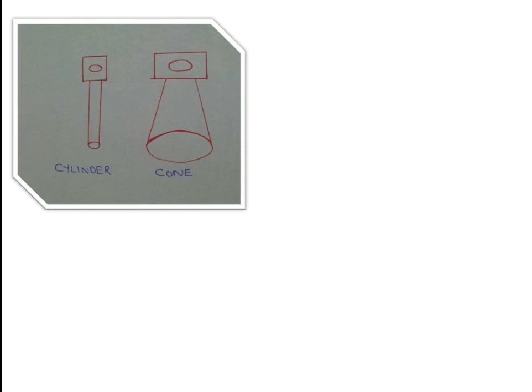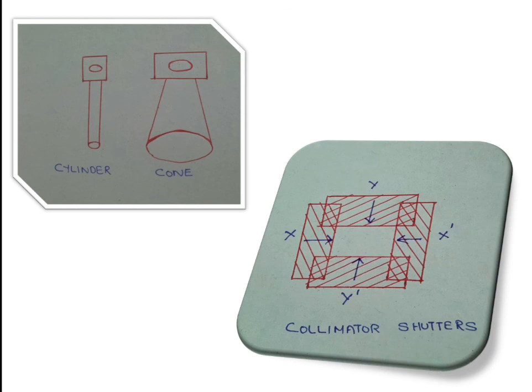Cylinders and cones are used in dental radiography and for skull radiography — specifically for x-ray examination of the mastoids, cones are used. For dental radiography we need to cover only a small area, so cylinders and cones limit the area of exposure to the opening of the cone or cylinder, ensuring other body parts are not unnecessarily exposed. The collimator has four shutters: Y, Y-dash, X, and X-dash.